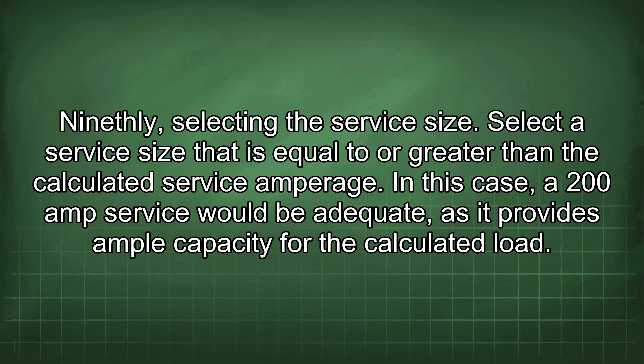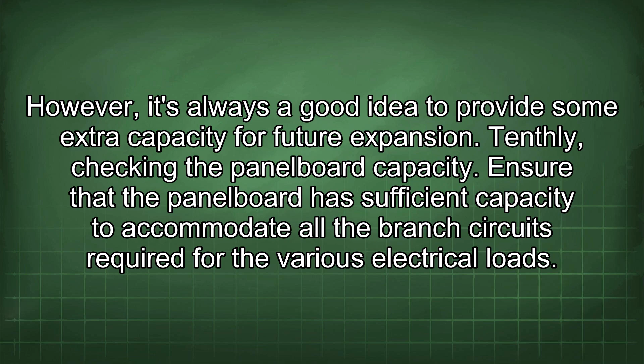Tenthly, checking the panel board capacity. Ensure that the panel board has sufficient capacity to accommodate all the branch circuits required for the various electrical loads. The panel board should have enough available spaces for circuit breakers to serve all the lighting, receptacles, appliances, and other equipment.